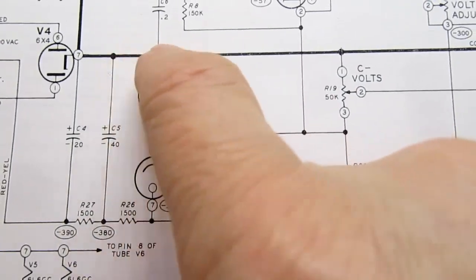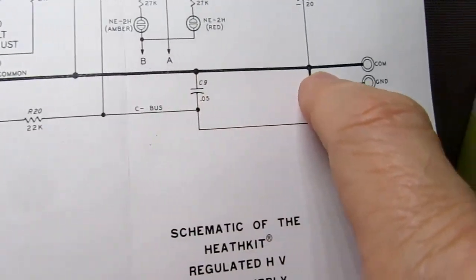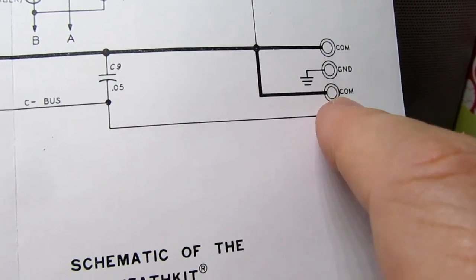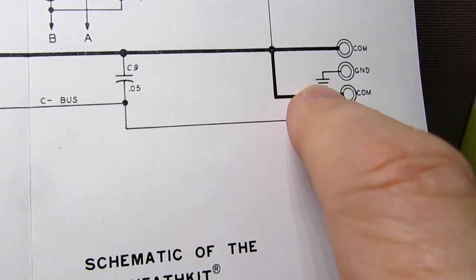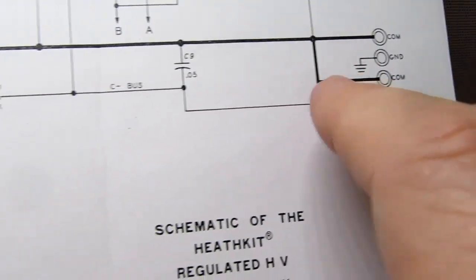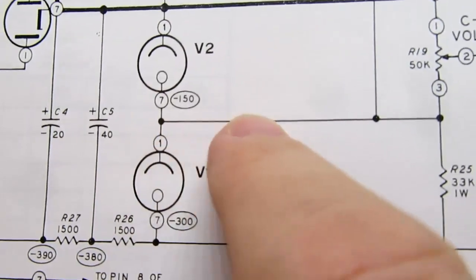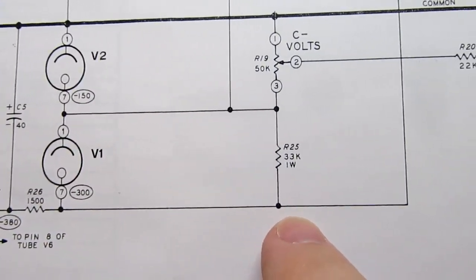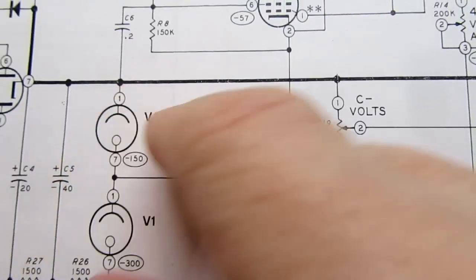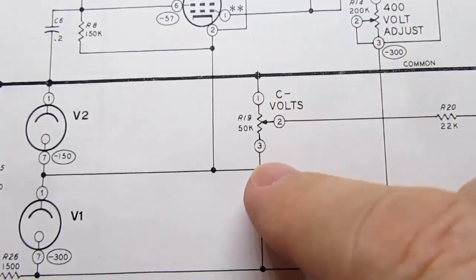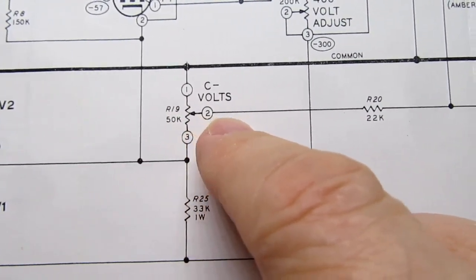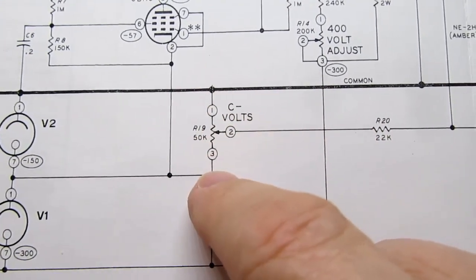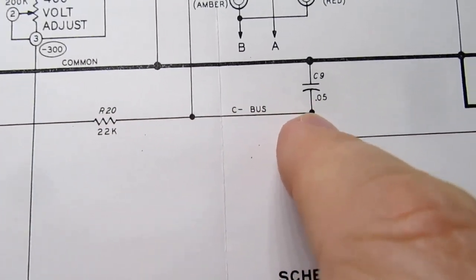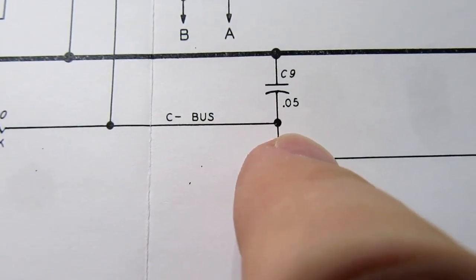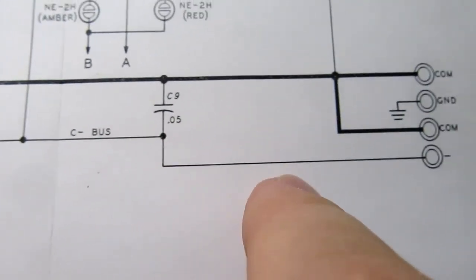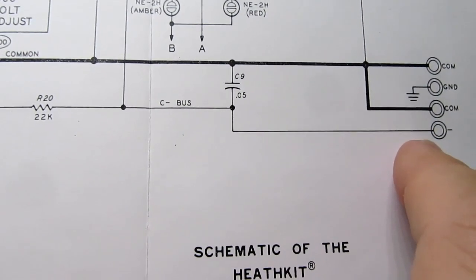So this is all reference to this point, which is circuit common. And it goes to two terminals marked common on the front panel. And either of those can be tied to chassis ground, which is also earth ground through the power cord, if you want it to be. This is considered the minus 150 volts, and down here it's considered minus 300 volts. The 150 volt one relative to common is applied across this pot, and as you adjust it, you get a voltage anywhere from 0 volts to 150 volts. It passes through this current limiting resistor. There's a very small capacitor here to shunt any noise to circuit common, and then it's applied to the output jack. So that's the entire circuit there.